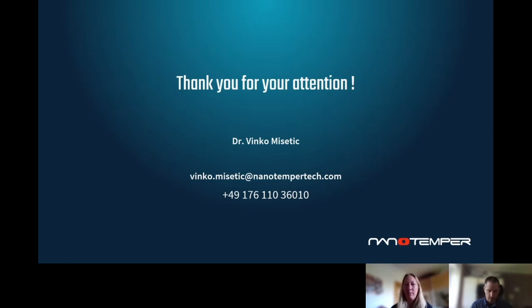My second question is, if I have a very thermostable protein, will it be possible to analyze it with the Prometheus? Yes. When it comes to stability, some people have really thermostable proteins that are stable above 100 degrees. For this, we have a special module, the so-called high temperature option, that allows you to measure thermostable proteins above 100 degrees. Working with small glass capillaries, it is also possible to seal the capillaries so that you don't get any evaporation, which takes 10 seconds. And then you can measure thermostable proteins.